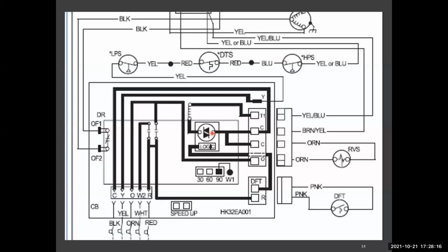And it's going to wait for the selected time. On this board that we have right now, we have it selected for 90 minutes. As long as that defrost thermostat stays closed for 90 minutes, that's when it'll go into defrost. It comes back, energizes the coil from the timer, and comes over from our R and sends two of the signals that we have. It's going to close this set of contacts, come back. There's your O. O is going to hit your reversing valve. That's going to switch it into the cooling mode.